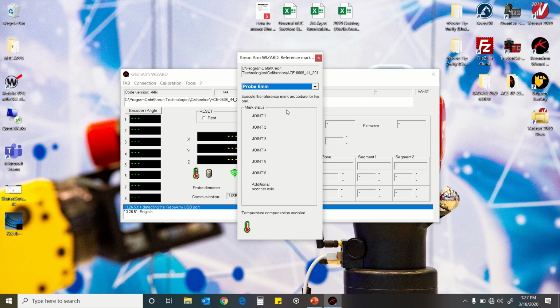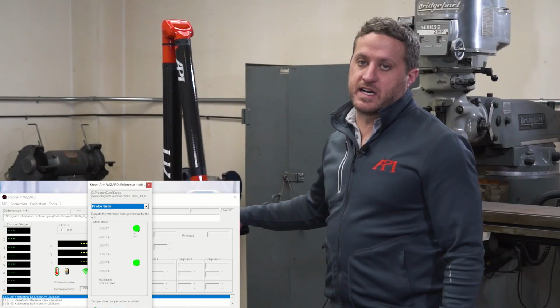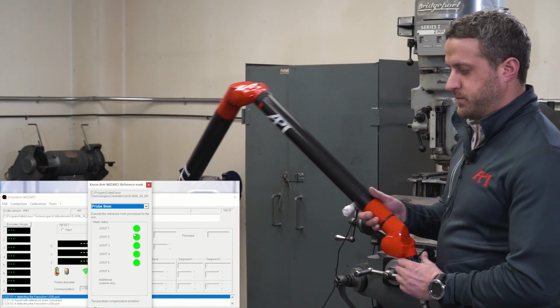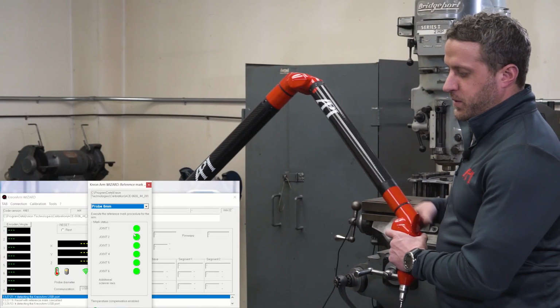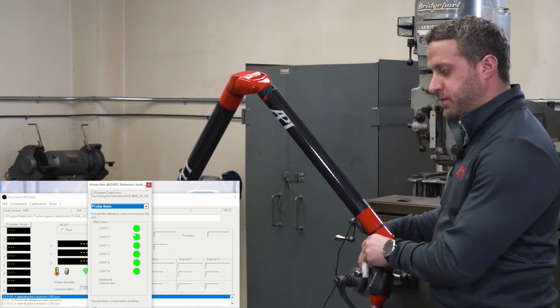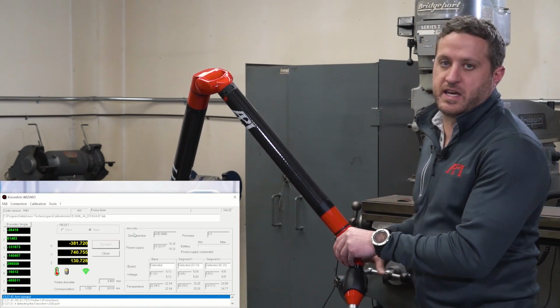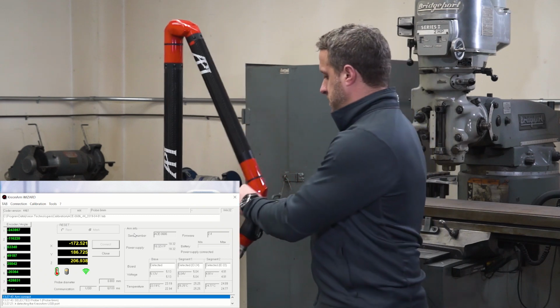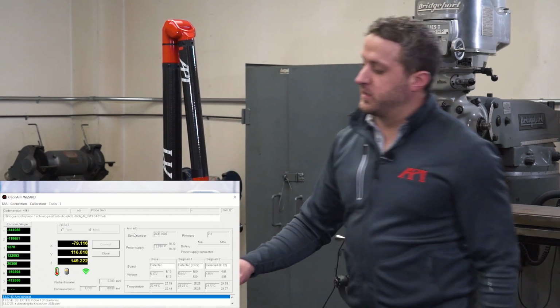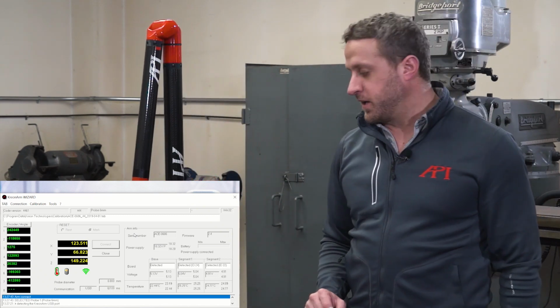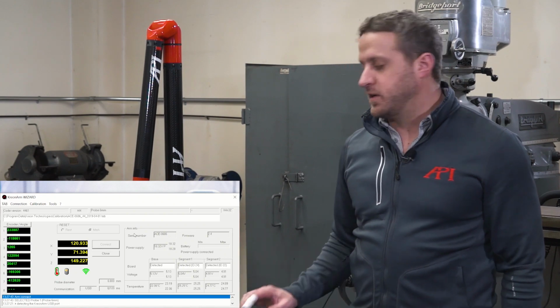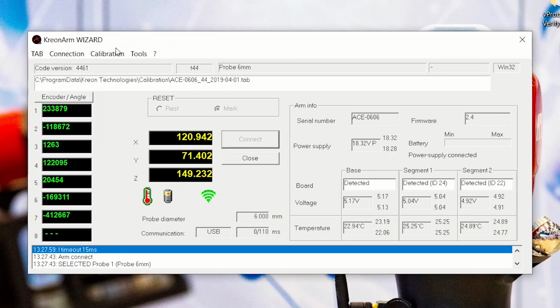Now it's asking us to unstow the arm to exercise each encoder. So as we move it, we can tell it's checking it off, and then finally the additional scanner axis. So now the arm wizard is reading out. We see numbers running. We're basically connected to it. From here, we can go into the calibration probes management.